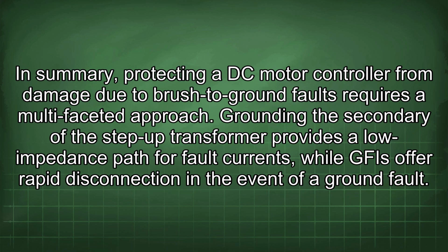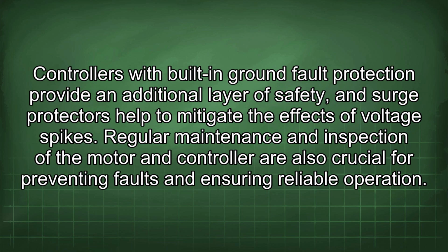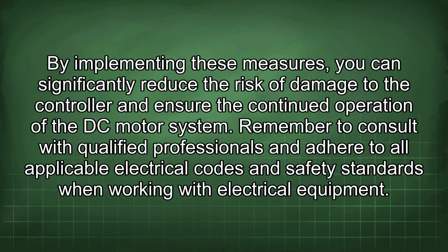In summary, protecting a DC motor controller from damage due to brush-to-ground faults requires a multifaceted approach. Grounding the secondary of the step-up transformer provides a low impedance path for fault currents, while GFI offer rapid disconnection in the event of a ground fault. Controllers with built-in ground fault protection provide an additional layer of safety, and surge protectors help to mitigate the effects of voltage spikes. Regular maintenance and inspection of the motor and controller are also crucial for preventing faults and ensuring reliable operation. By implementing these measures, you can significantly reduce the risk of damage to the controller and ensure the continued operation of the DC motor system.